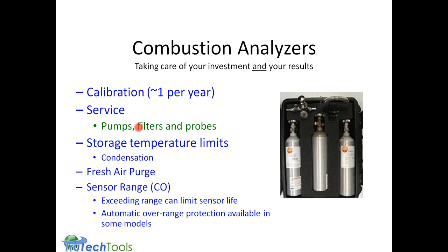Service that may be required are pumps, filters, and probes. In the case of the 327, there is a filter that's in the end of the probe. It's a yellow cone type filter. It's made of a plastic breathable polymer, and it's yellow in color, and that cone will get dirty when it gets contaminated by any kind of soot or dust. When that's discolored, then you want to remove that filter and replace it. Every meter comes with 10 new filters, so you're set to go for quite a long time.